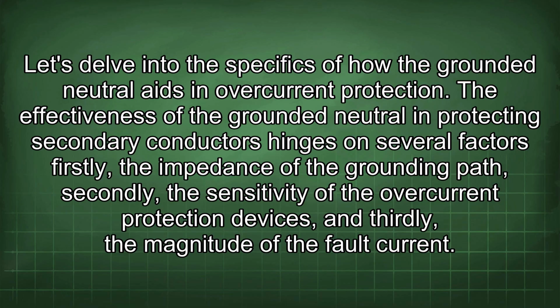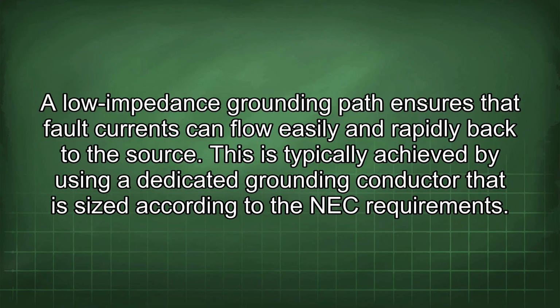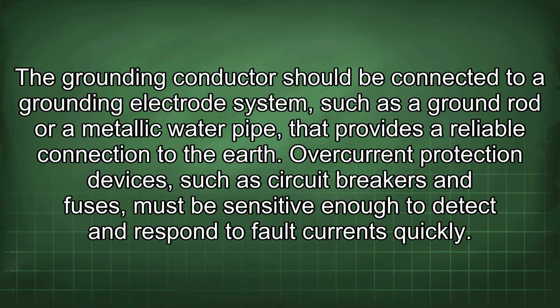The effectiveness of the grounded neutral in protecting secondary conductors hinges on several factors. Firstly, the impedance of the grounding path. Secondly, the sensitivity of the overcurrent protection devices. And thirdly, the magnitude of the fault current. A low impedance grounding path ensures that fault currents can flow easily and rapidly back to the source. This is typically achieved by using a dedicated grounding conductor that is sized according to the NEC requirements. The grounding conductor should be connected to a grounding electrode system, such as a ground rod or a metallic water pipe that provides a reliable connection to the earth.